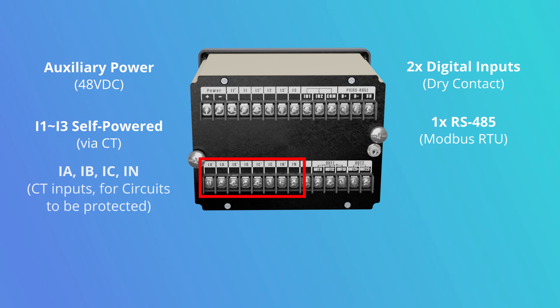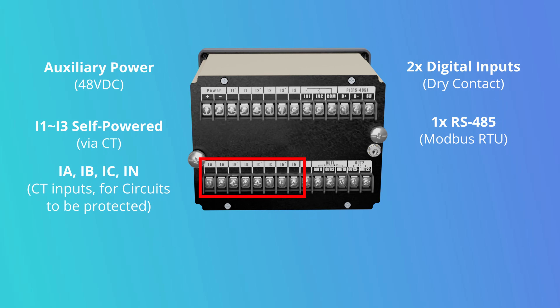IA, IB, and IC are the terminals for connecting CTs on the circuits to be protected from overcurrent, overload, unbalance, etc. IN is the terminal for connecting a neutral CT or external zero-sequence CT for ground fault protection.